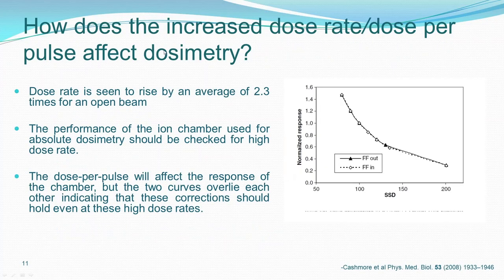How does the increased dose rate or dose per pulse affect dosimetry? Dose rate rises by about 2.3 times for an open beam in Triple F compared to Double F. The performance of the ion chamber at such a high dose rate has to be checked. Significant information is given in the paper by Cashmore et al. in Physics in Medicine and Biology, 2008, where they studied dose per pulse effects. They found that the variation between Double F and Triple F is not significant, but it is good practice to check for your own chamber.